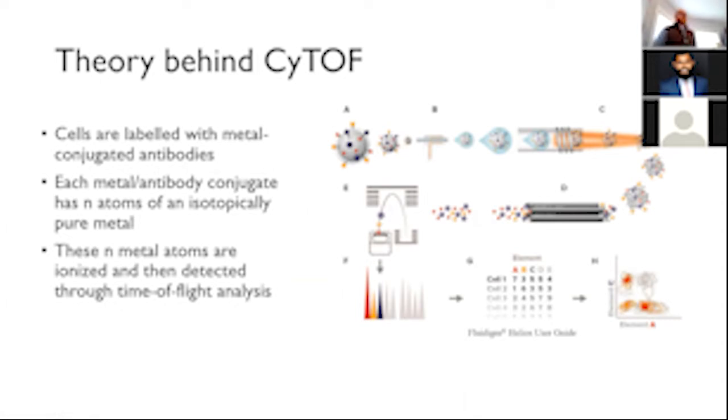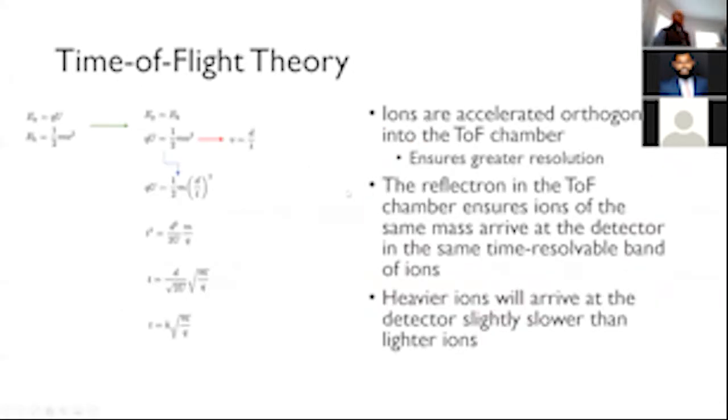So briefly, just a quick theory behind CyTOF before we really dig in, just for a high-level overview. So as most of you probably know, the cells are labeled with metal conjugated antibodies. They're then put through a nebulizer, aerosolized, and then injected into a plasma, where they're atomized and ionized. And then they go through a series of filtration and focusing steps, and then are detected based on their time of flight, exported as unique spectra, and then transformed into FCS files. And we'll get into each of these components along the way.